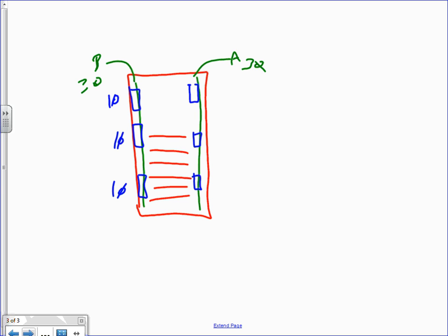We used to see three-phase 4-wire quite a bit. What we're seeing more now is 208 volt single phase within this strip, so just the three-phase with no neutral coming in, and we're seeing that more and more. So we see these little two-pole breakers built into the plug strip, sometimes grouped together. All the outlets here might be off phase AB, 208 volt single phase, the ones here off AC, and the ones over here off BC — 6 or 8 plugs off BC, and the same for the other two.